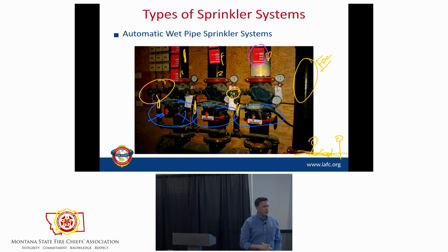Will your fire pump ever tell you anything? This is an interesting part to have a conversation with our fire pump operators. So they've got 5-inch Storz, deuce and a half, so however you hook up your FDCs, right? And you're pumping in, you've got it at 150. And like a good pump operator, you kind of go see what everything else is going on because you're bored. You're not even the attack line, right? You are bored. And you walk back to your truck and all of a sudden your discharges are at 100 PSI.